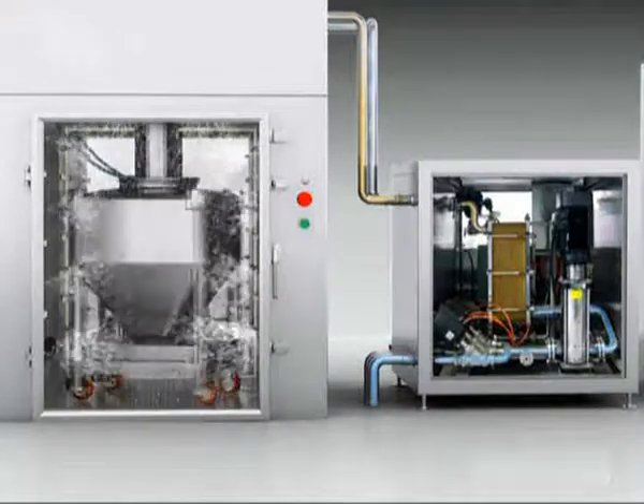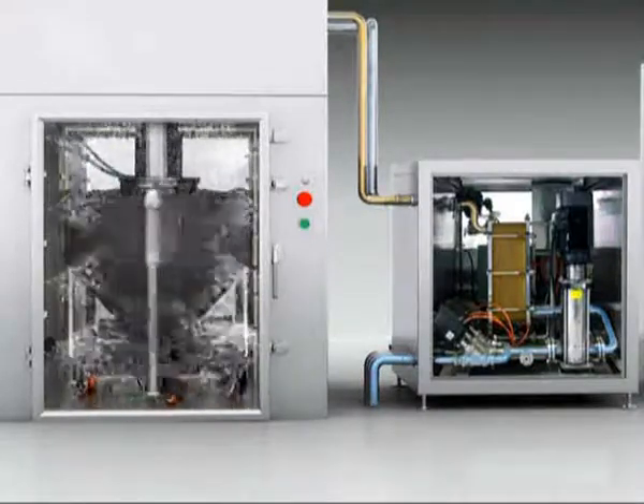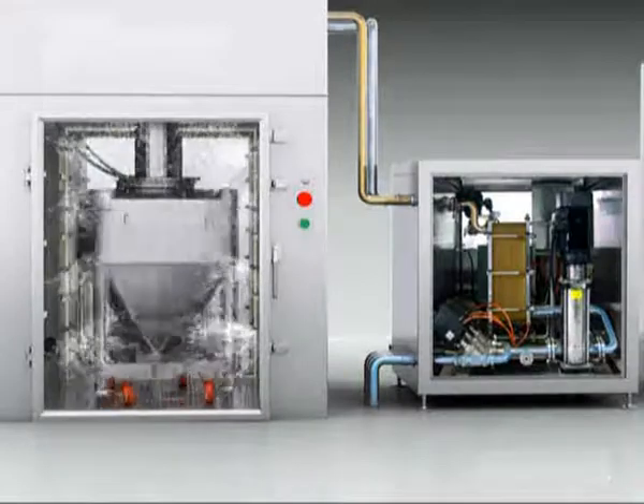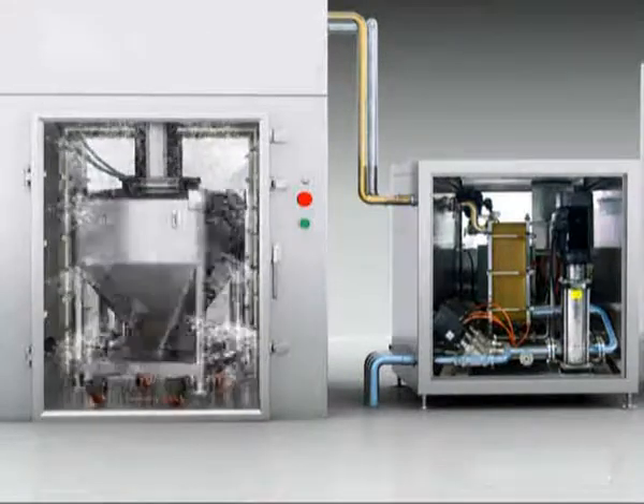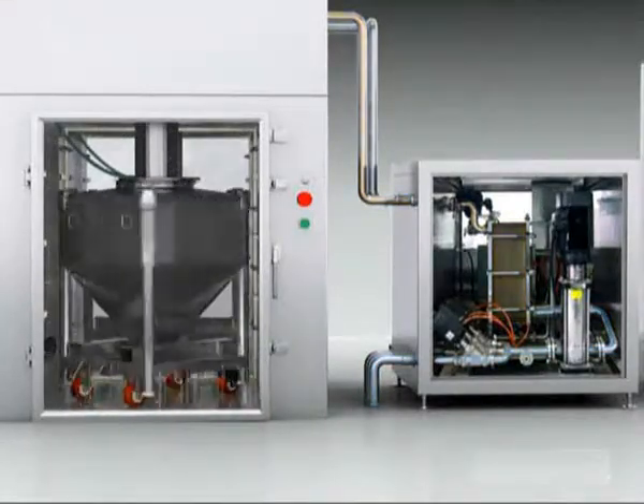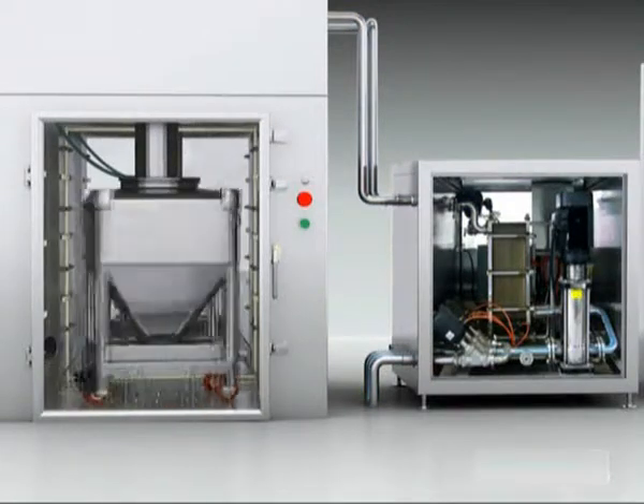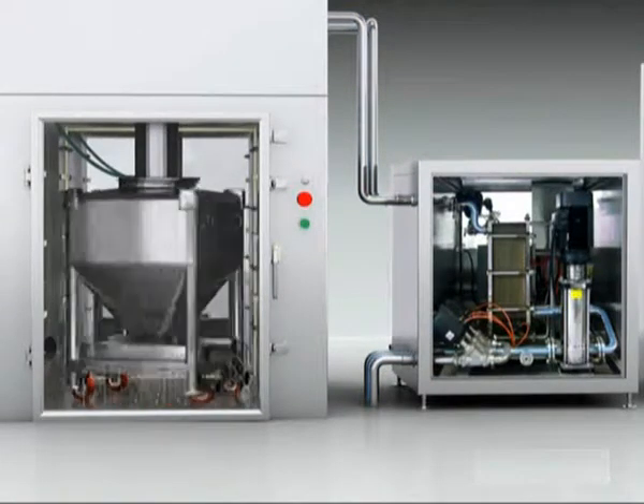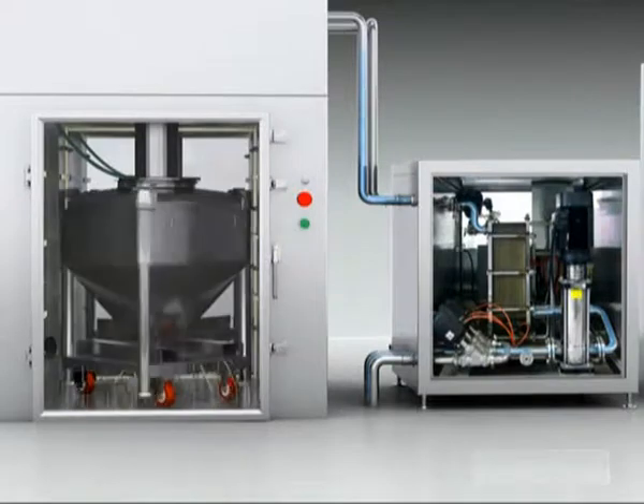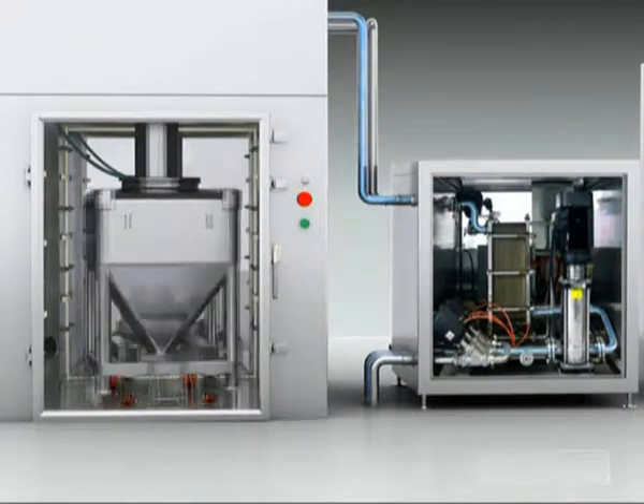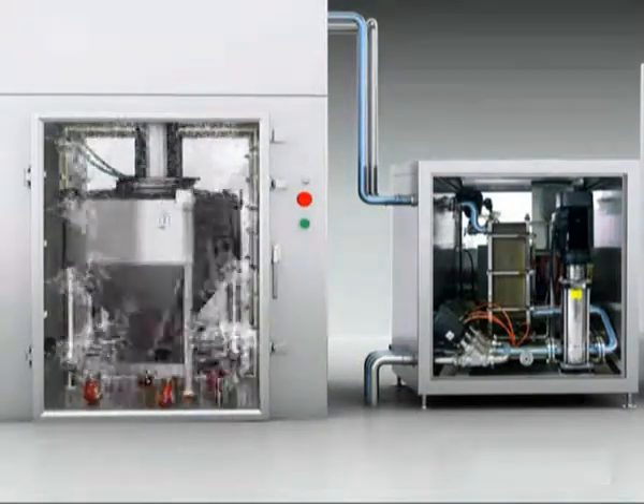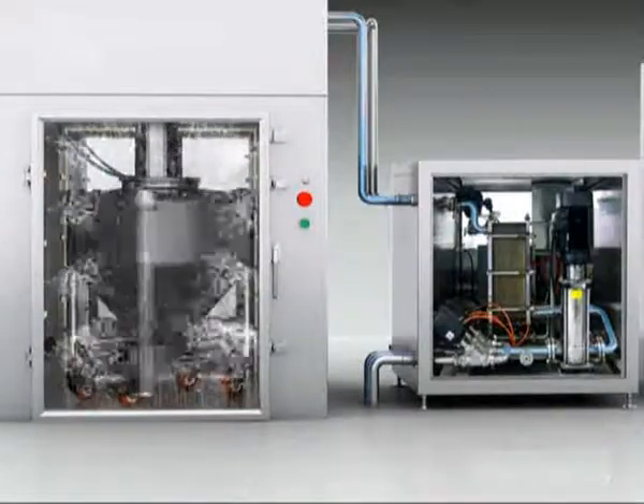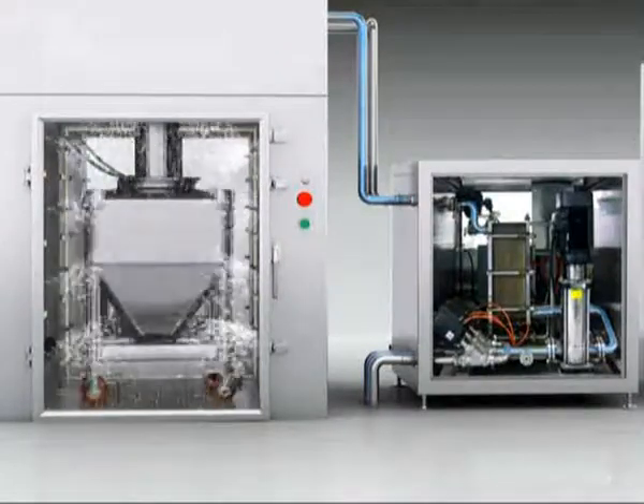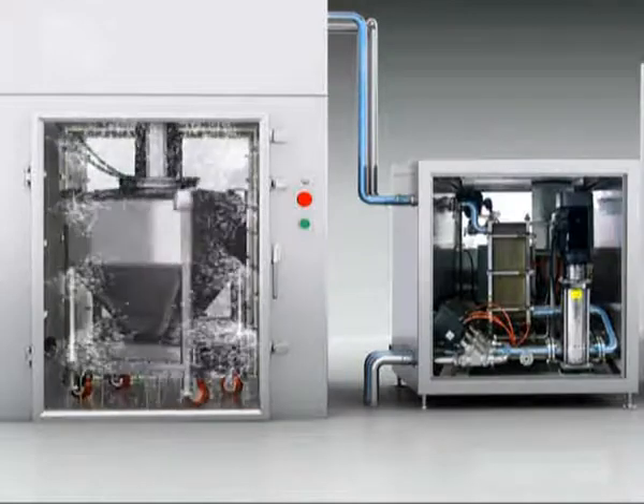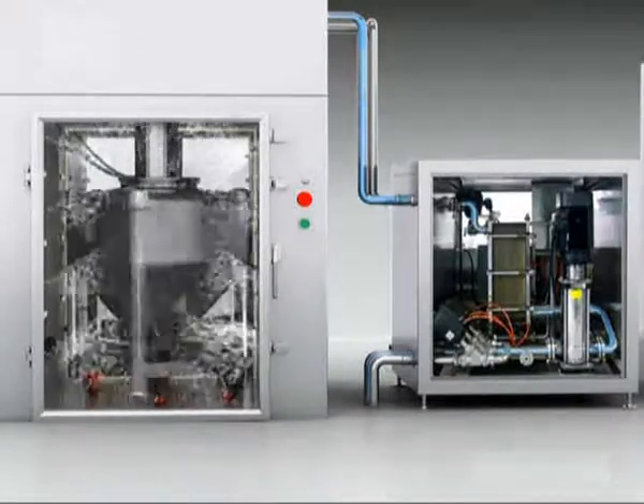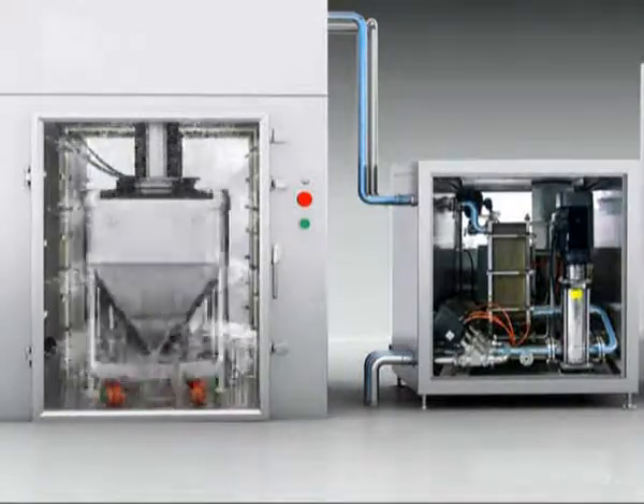After the hot water washing procedure, system loads automatically the detergent washing procedure. In this stage, the detergent unit in the pump station prepares the detergent solution, and the boost pump increases the pressure of the detergent solution. Then it flows through the piping to the top washing board and the nozzles on the washing chamber walls for internal and external surfaces cleaning. Finished detergent washing cycle. Pure water washing runs as final cleaning cycle.